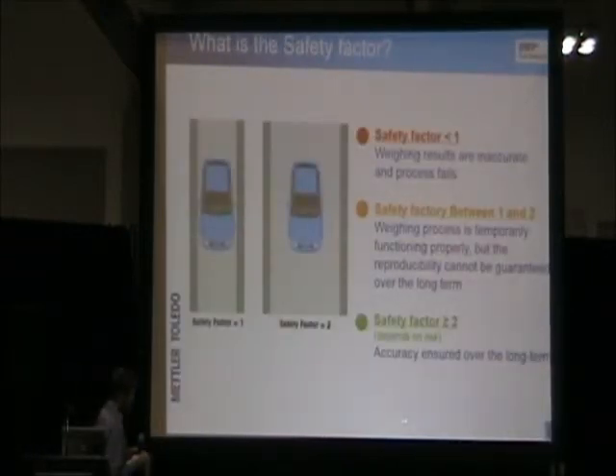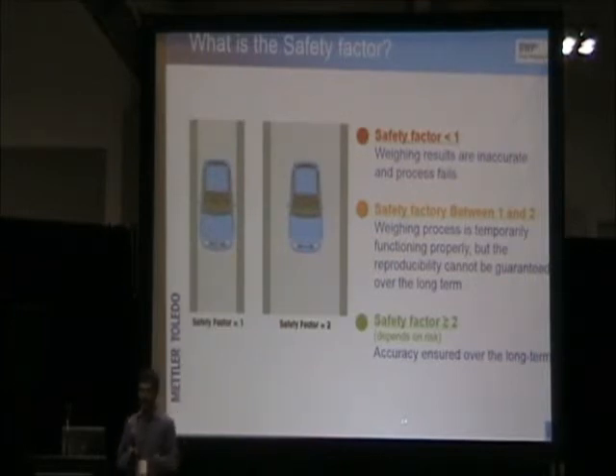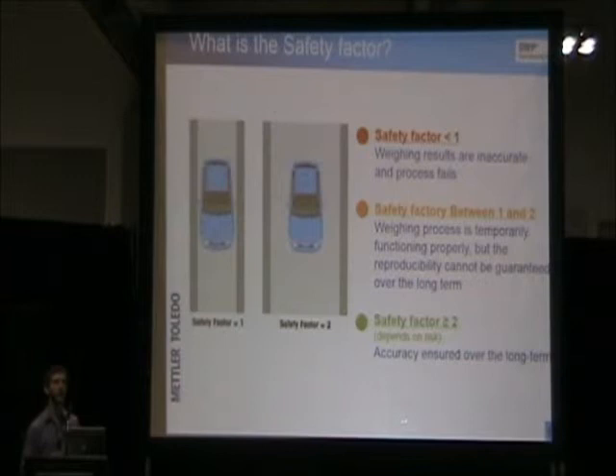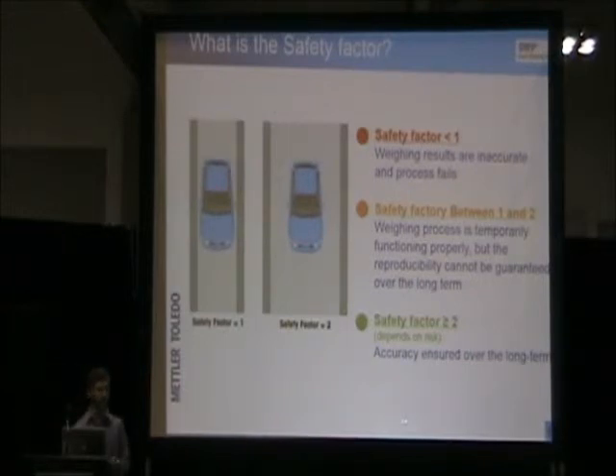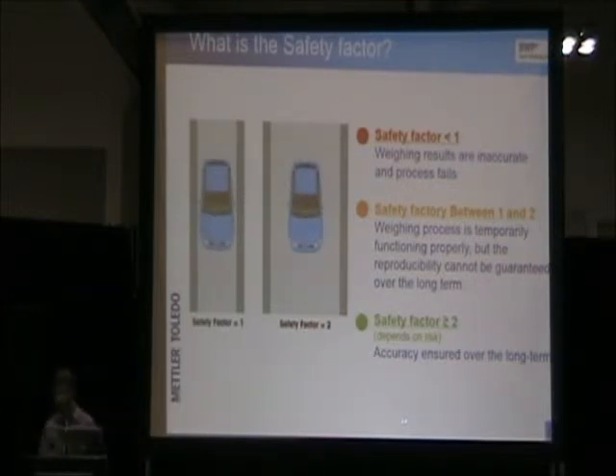I'm going to give you an explanation for kind of a real-life scenario here. Let's say that, again, in my prior example, you established a minimum weight of 30 milligrams on a 5-place analytical balance. That would be a safety factor of 1, meaning that when you established that minimum weight of 30 milligrams, that was done after calculating, using the repeatability, of a stainless steel calibration weight. But again, we're not weighing stainless steel calibration weights when we're doing everyday weighing.